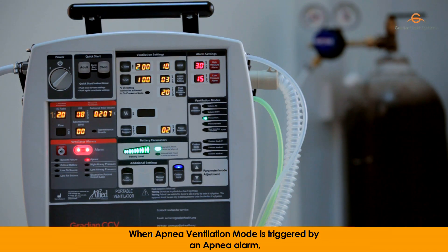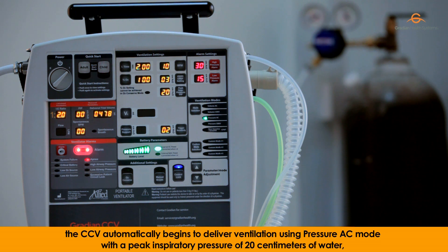When apnea ventilation mode is triggered by the apnea alarm, the CCV automatically begins to deliver ventilation using pressure AC mode with a peak inspiratory pressure of 20 cm of water, a respiratory rate of 10 breaths per minute, an I-time of 2 seconds, and a PEEP of 3 cm of water.